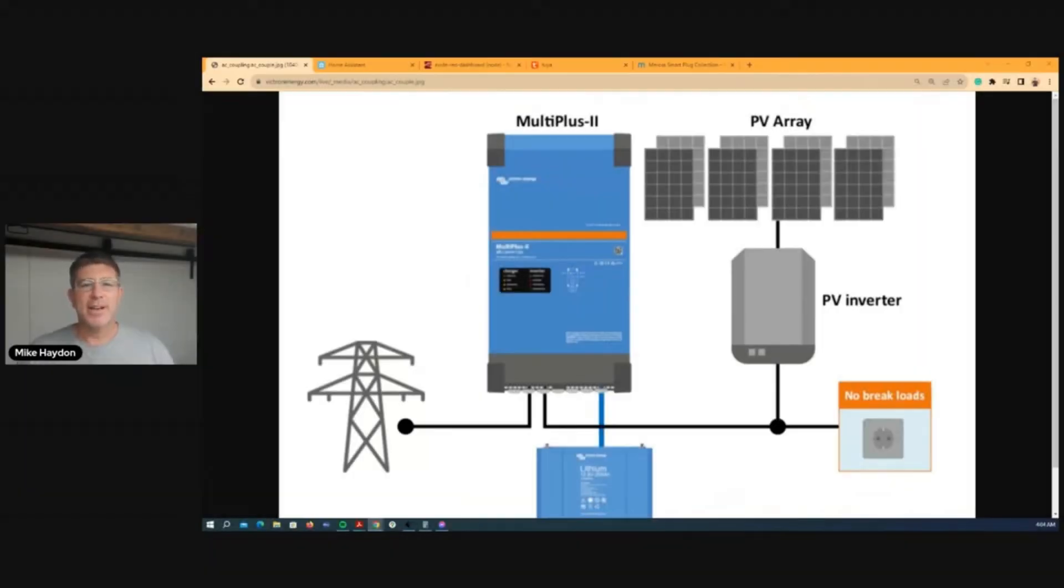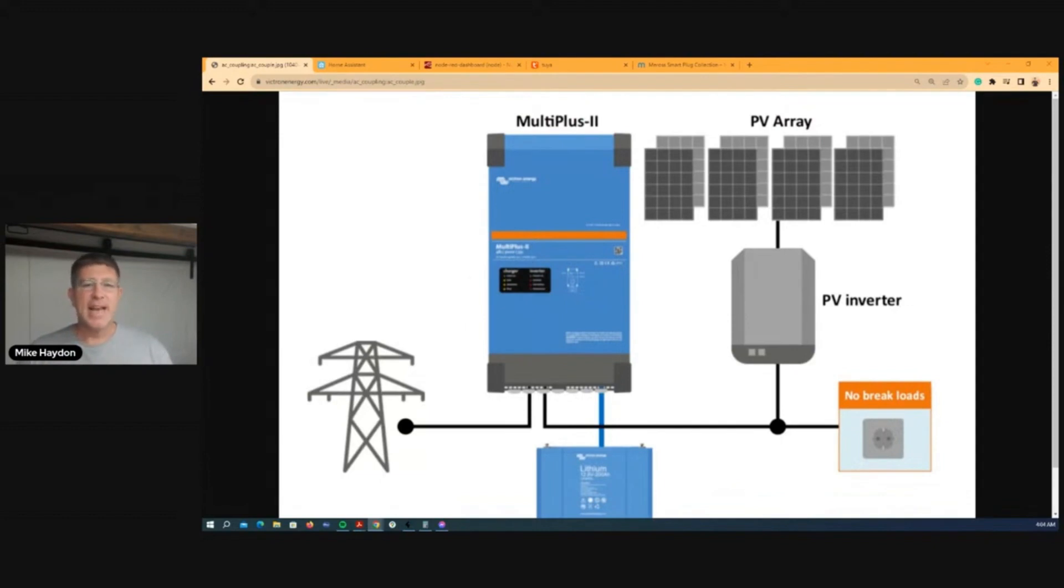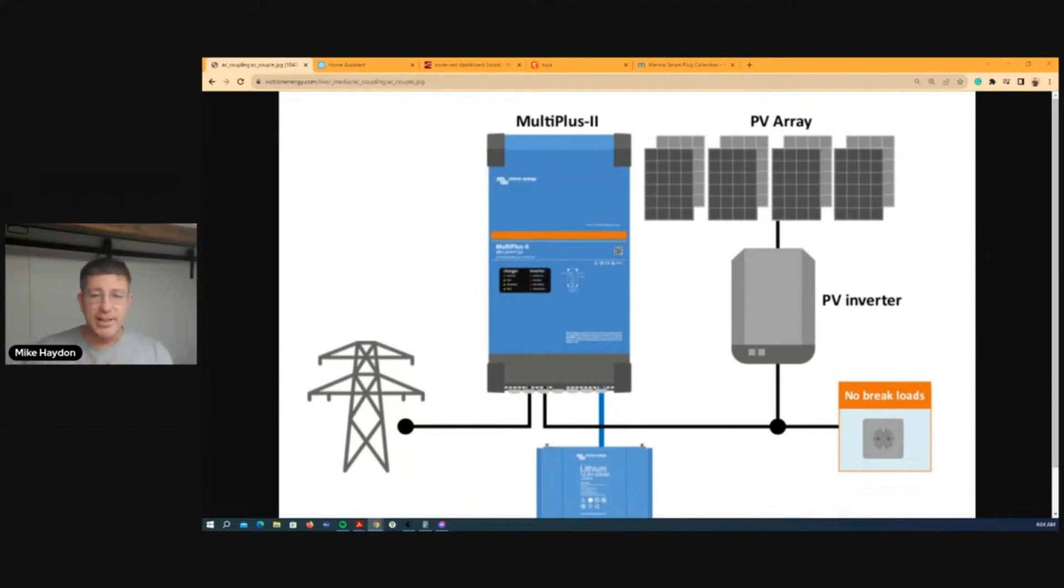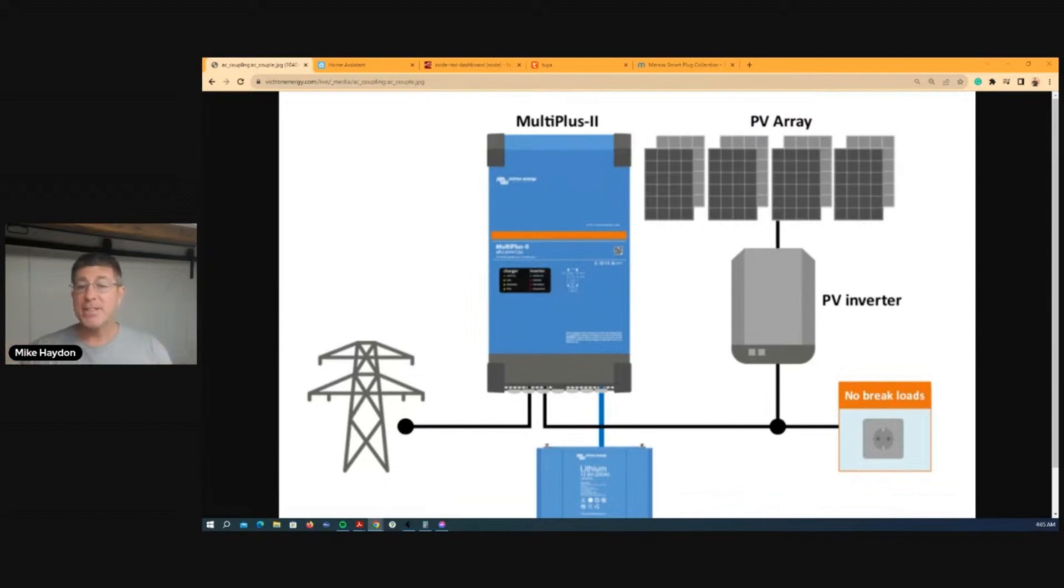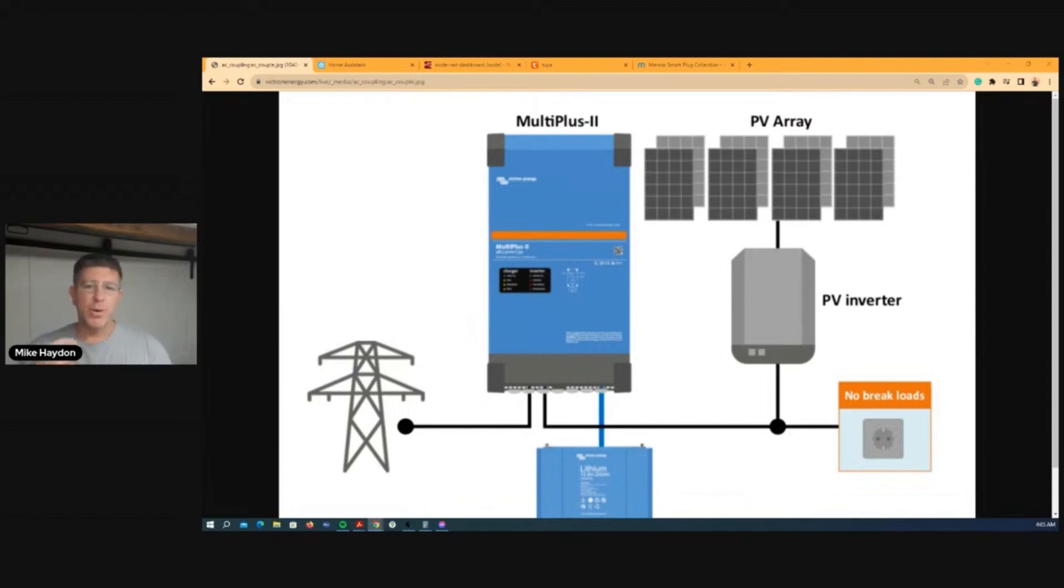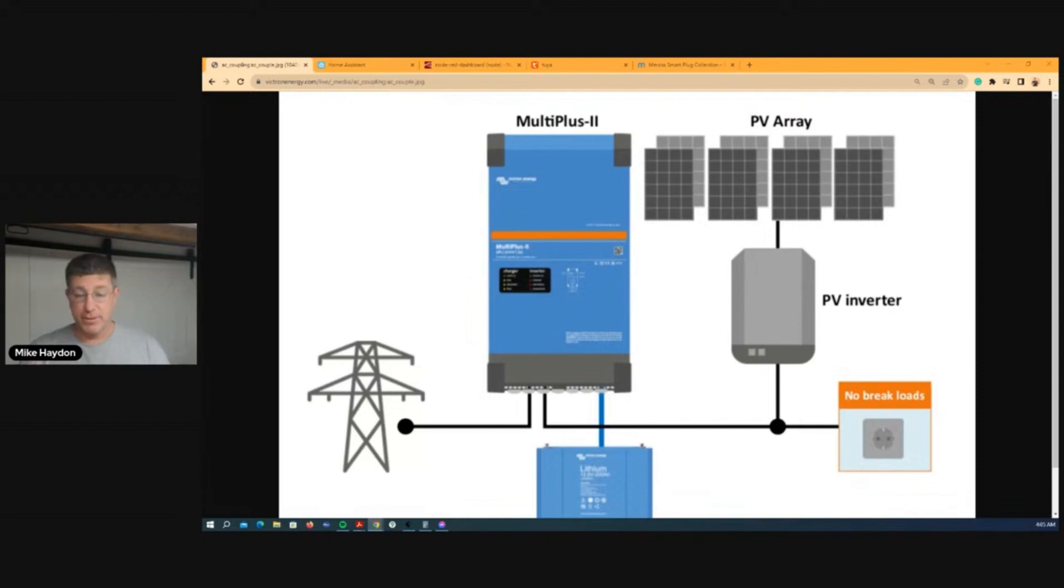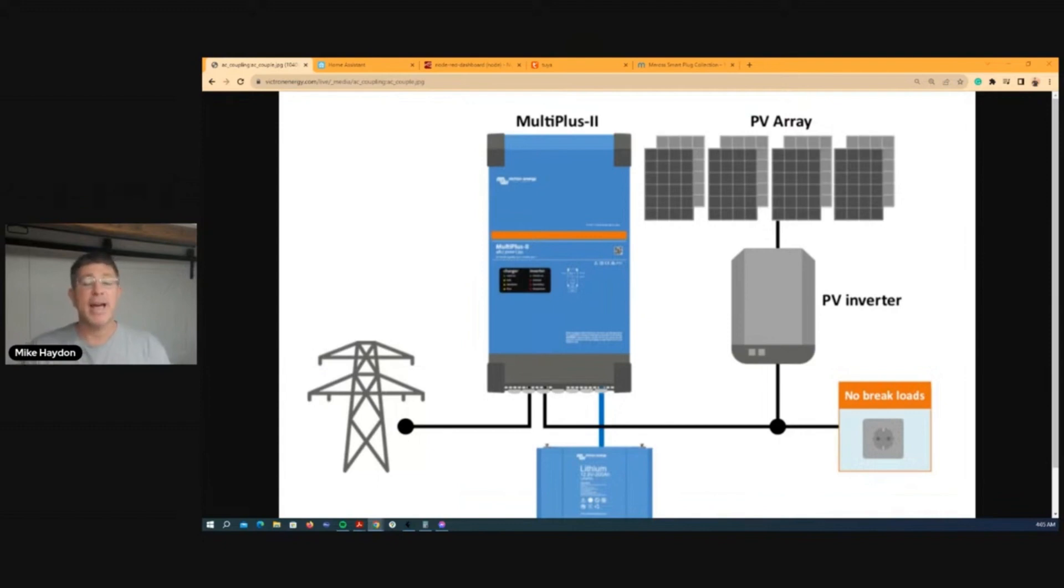When you're off-grid, it's an attitude of use it or you lose it. Basically, the energy's got nowhere to go. You might have a PV inverter or grid-connected inverter or AC coupled inverter, and then you could have panels direct to batteries depending on the system design. What happens when the batteries are full, the energy's got nowhere to go, so what the Victrons do is they do a frequency shift and they control the grid connect inverter or tell the MPPT that we don't need any extra power, batteries are full, and they turn down.